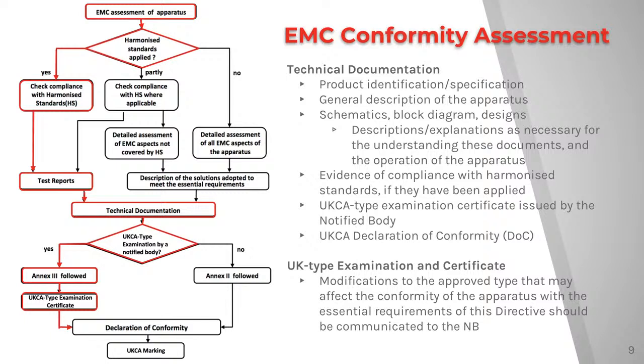And so moving on with the EMC conformity assessment, these are the things that will be required. We have the technical documentation, which is the product identification and specifications, the general description of the apparatus, schematics, block diagrams, designs, and descriptions and/or explanations as necessary for the understanding of these documents and the operation of the apparatus. Evidence of compliance with harmonized standards, if they have been applied. A UKCA type examination certificate issued by the notified body, and a UKCA declaration of conformity.